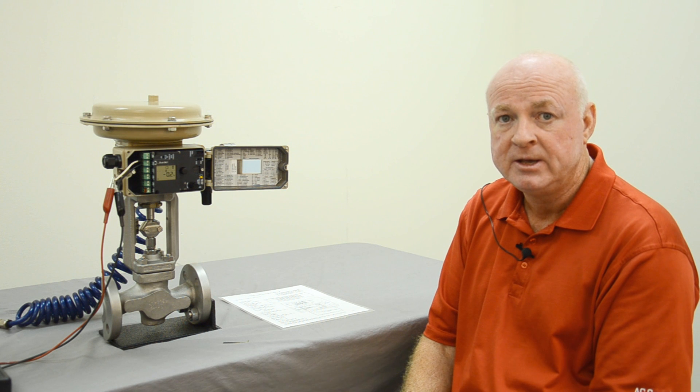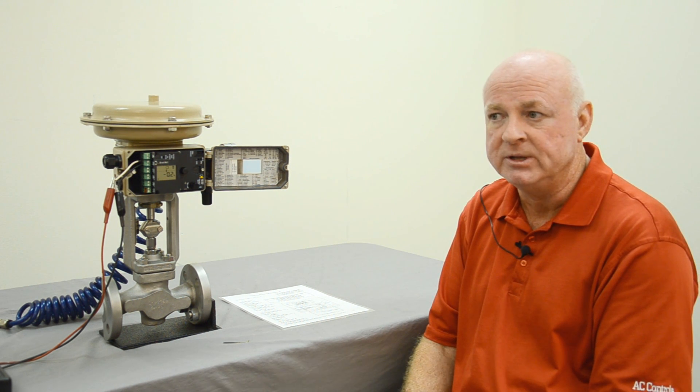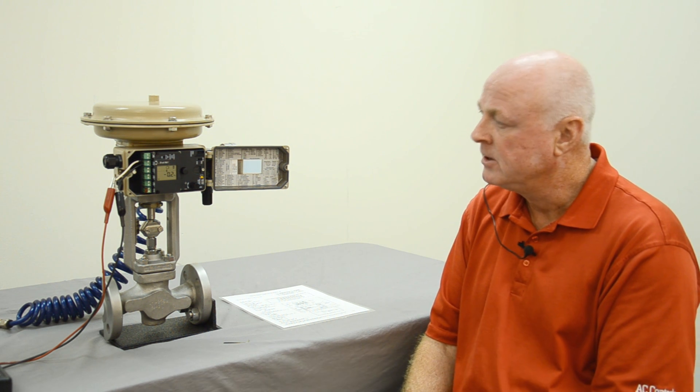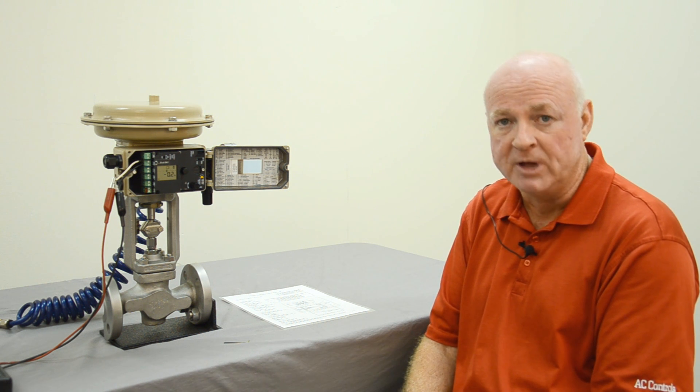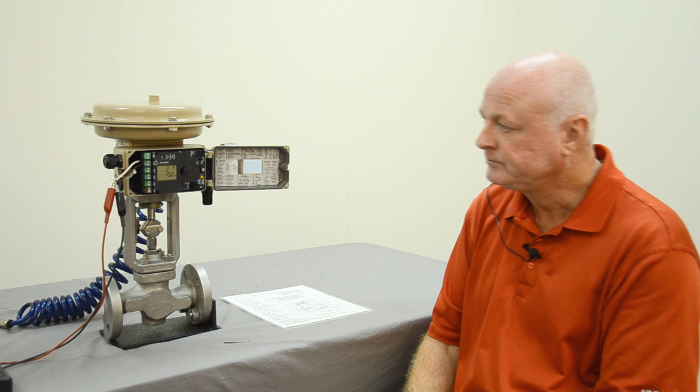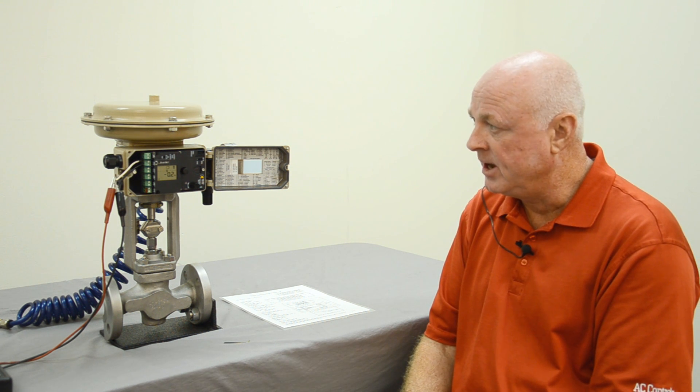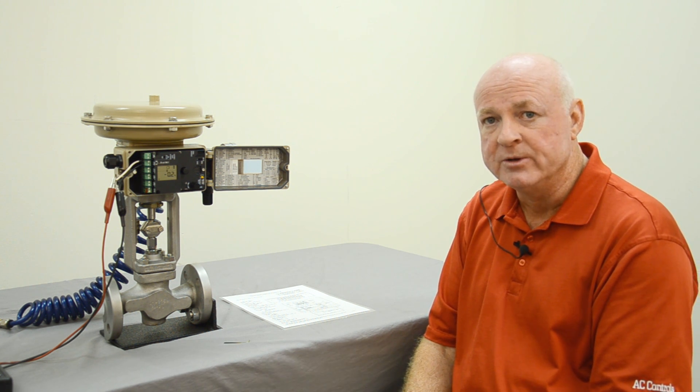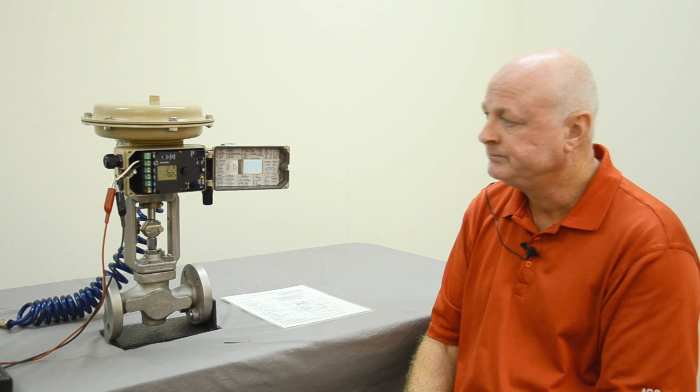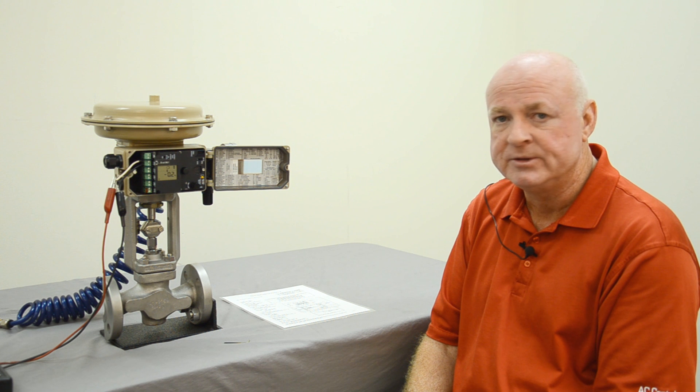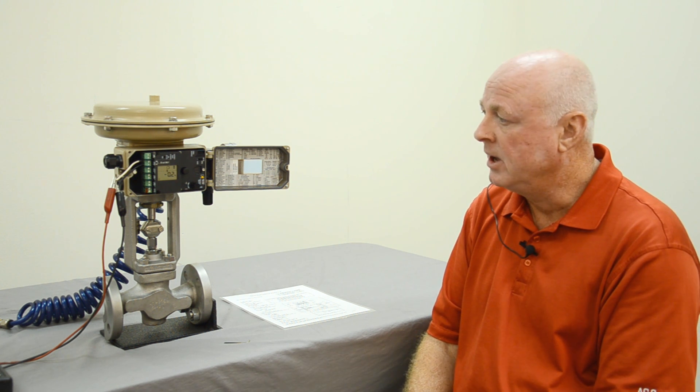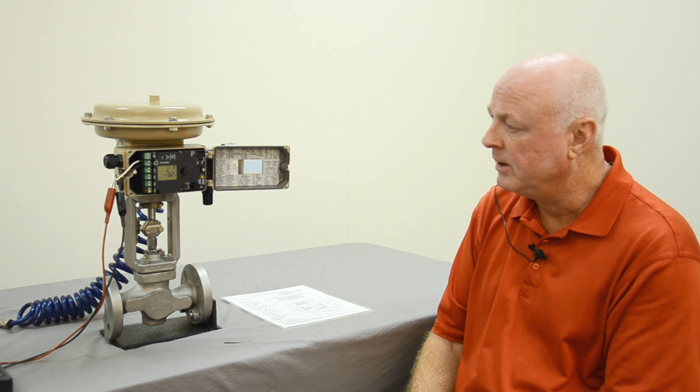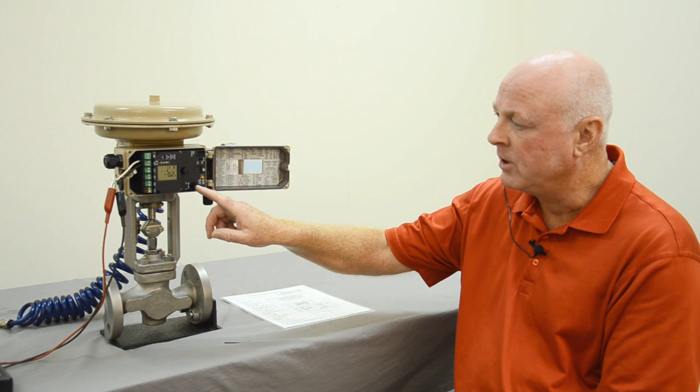So for example, we have fifteen PSI spring range. If we have forty pounds of air, then that's above the range and lower than the maximum air supply that the positioner can handle. So once you've got your air supply hooked up and your milliamp signal, the positioner will go through a self-diagnostics. Once it goes through its self-diagnostics, then you're ready for configuration.